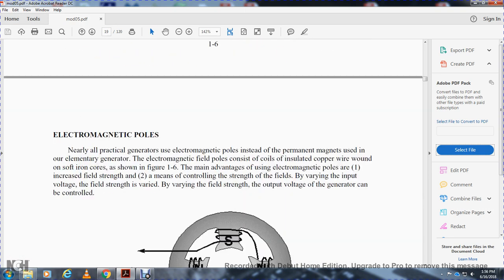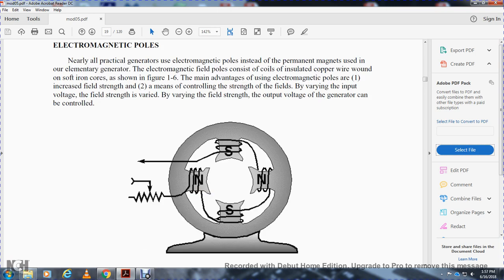Electromagnetic poles: nearly all generators use electromagnetic poles instead of the permanent magnets of the elementary generator. Electromagnetic field poles consist of coils of insulated copper wire wound on a soft iron core, as shown in figure 1-6. The main advantages of electromagnetic poles are increased field strength and the ability to control field strength by varying the input voltage. By varying the field strength, the output voltage of the generator can be controlled. Figure 1-6 shows a four-pole generator without armature.